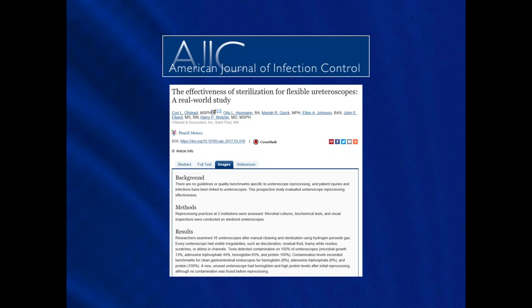But look at this study that looked at flexible ureteroscopes being used through the bladder in the ureter in a fluid environment. They don't really get grossly dirty with bioburden after use. But they looked at 16 flexible ureteroscopes after cleaning and after sterilization with hydrogen peroxide gas. All 16 of these scopes, 100%, had residual contamination in the form of either ATP, hemoglobin, protein, or microbial growth. That's pretty compelling information right there, that after cleaning, after sterilization, these scopes still had contamination on them.